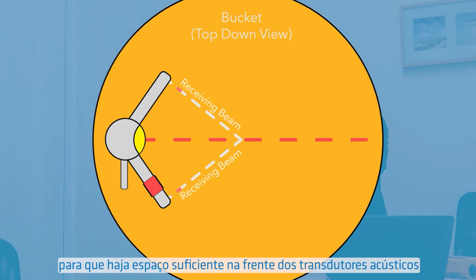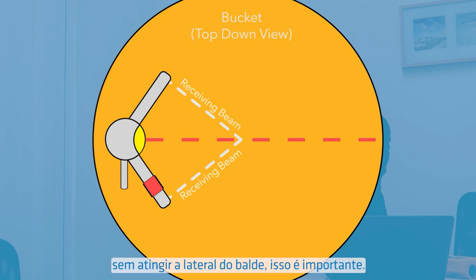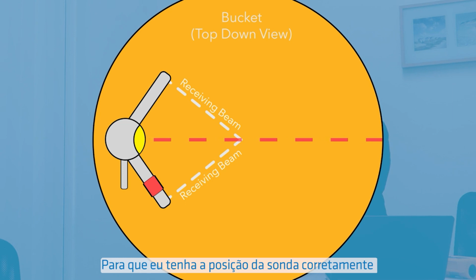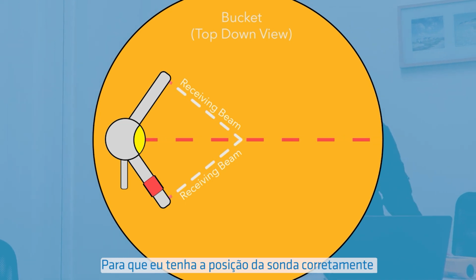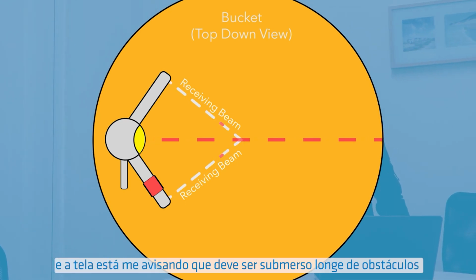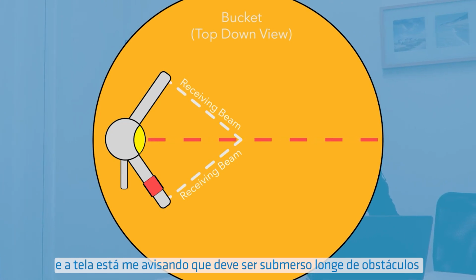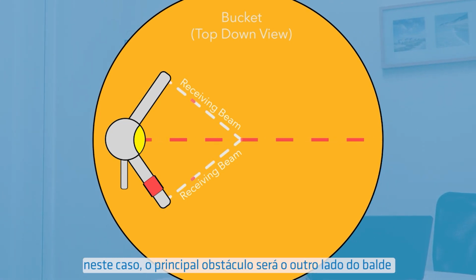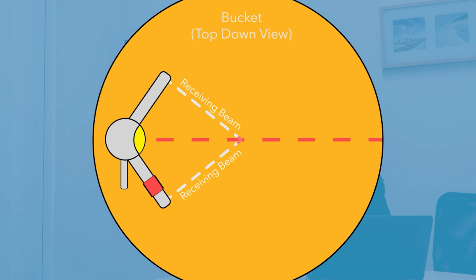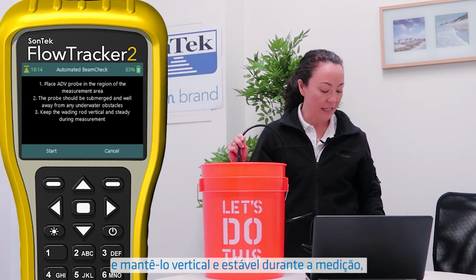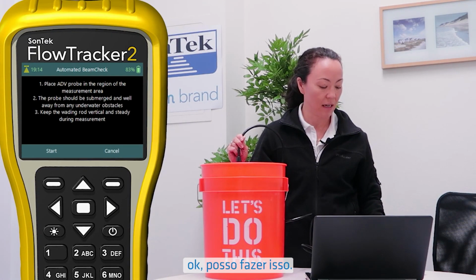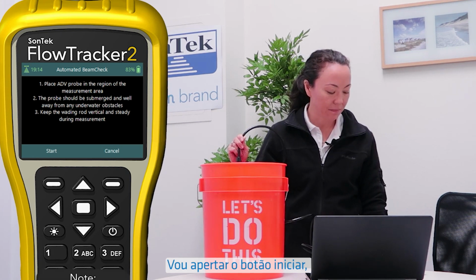So move the instrument a little bit back towards the edge of the bucket so there's enough space in front of the acoustic transducers without hitting the side of the bucket. That's important. So I have the probe positioned properly, and the screen is prompting me. It should be submerged away from obstacles. In this case, the main obstacle is going to be the other side of the bucket. And keep it vertical and steady during the measurement. Okay, I can do that. I'm going to hit the start button.